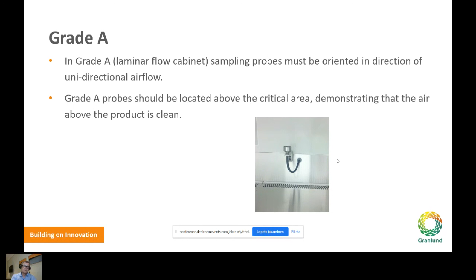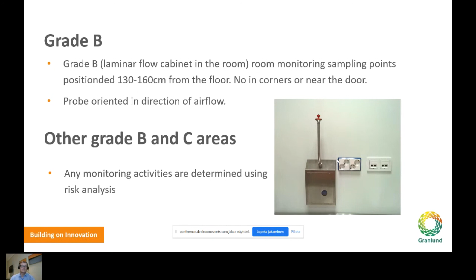And here is an example of grade B sample points, which are positioned 1.3, 1.6 meters from the floor, not in corners or near the doors, and probe oriented in direction of airflow. And other grade B and C areas, the monitoring point activities, they are determined using risk analysis. And here are some photos from the collection system of different rooms.